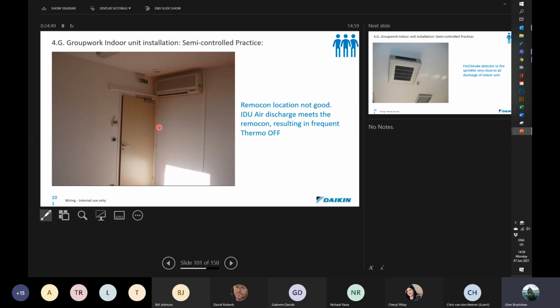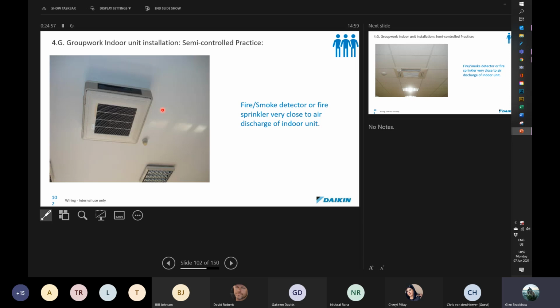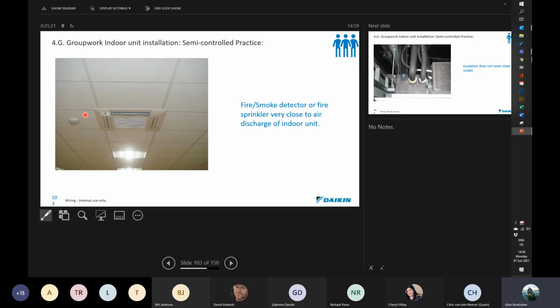Don't put it in an area where the air from the unit or from a diffuser is going to blow directly onto it, okay? The next thing to have a look at is don't put units close to smoke detectors. Newer type smoke detectors have a bit of a problem because they don't use the radioactive ones anymore in determining the difference between mist and smoke. So we don't want to be setting off fire alarms unnecessarily. And there's a smoke detector over there, and also sprinklers. Keep units away from sprinklers.